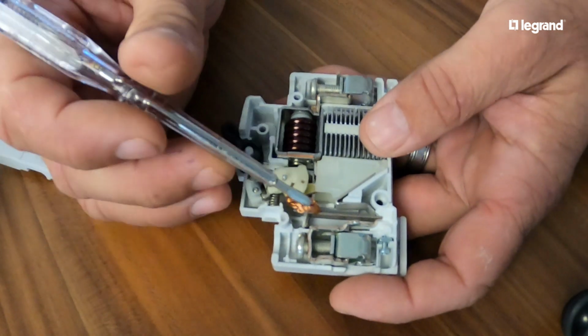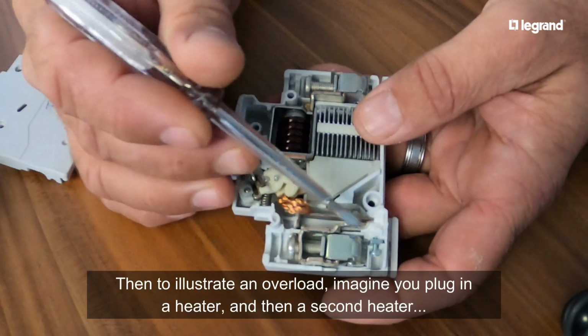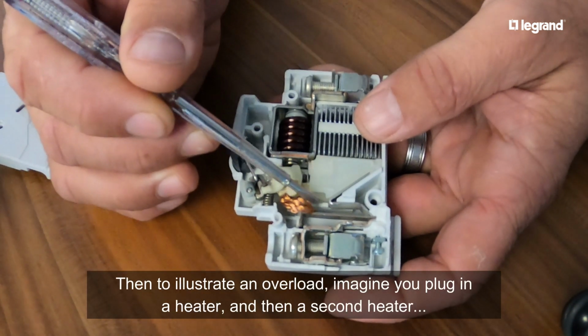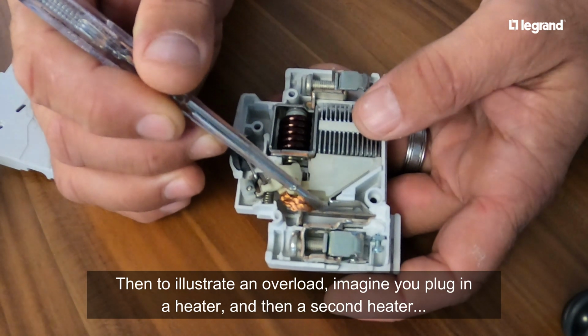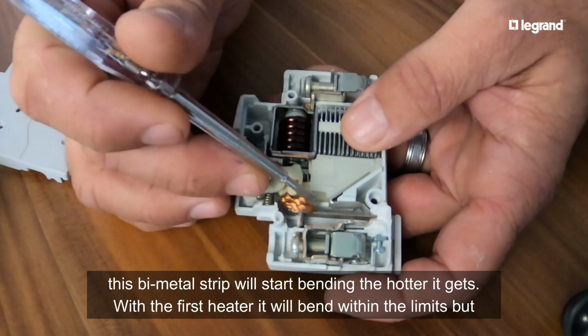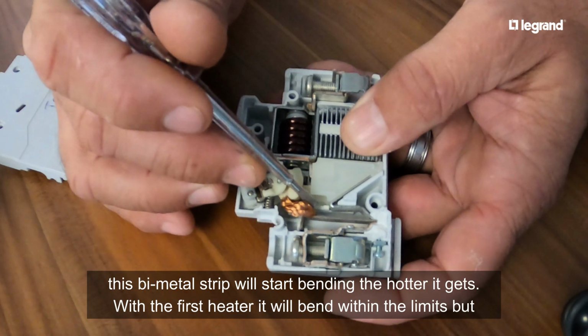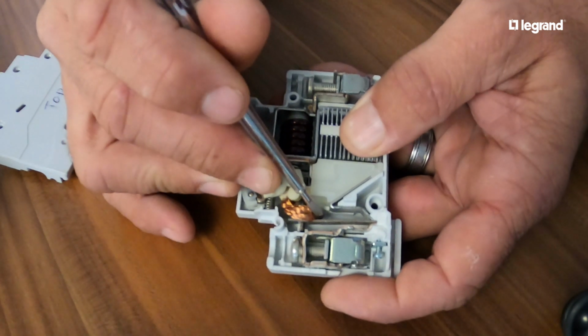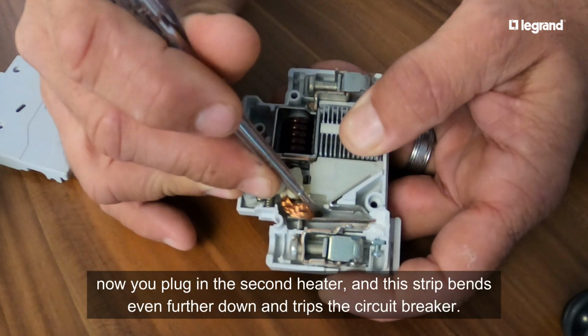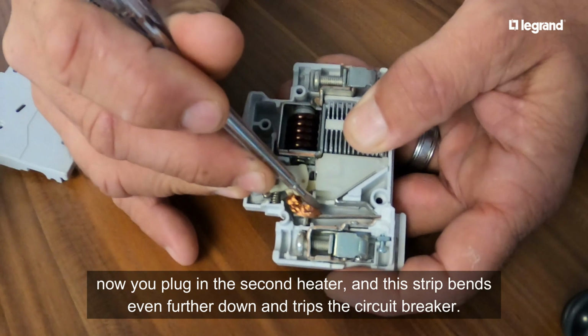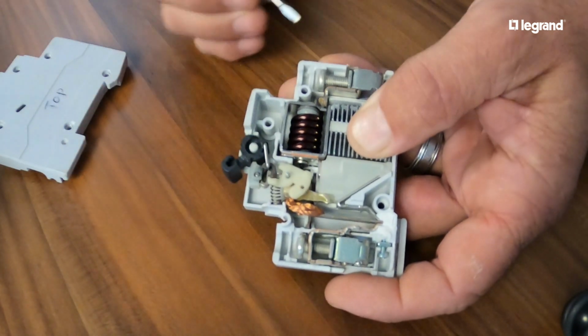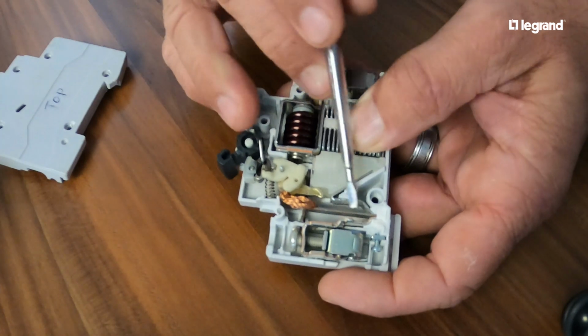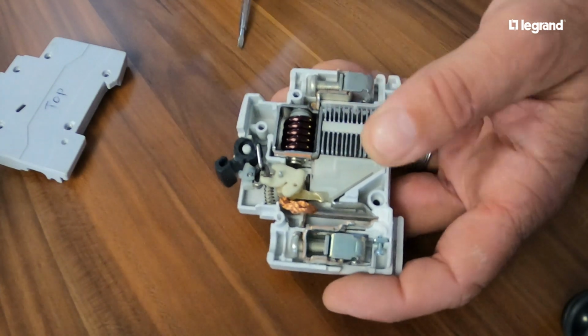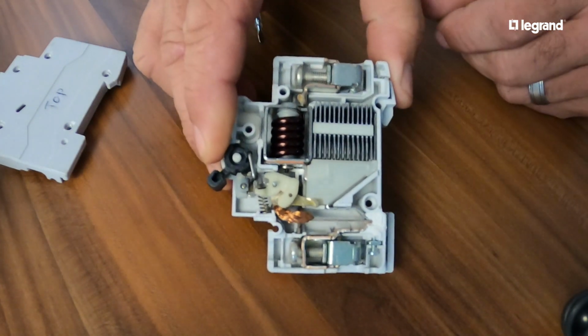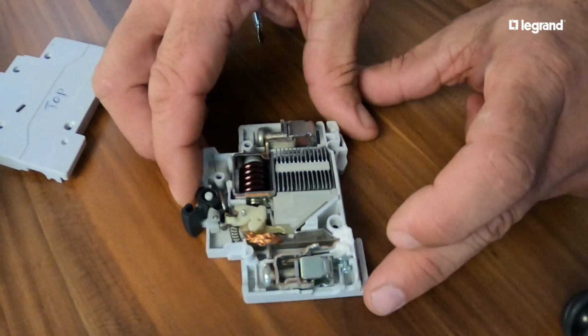Now imagine you plug in a heater. This little strip here is designed in such a way that it starts bending the hotter it gets. So the first heater that you plug in will start bending it within the limits. Now the second heater that you plug in bends it even further down and plop, the circuit breaker trips. So that's your overload protection right there. And basically that explains the inner workings of a circuit breaker, simple as that.